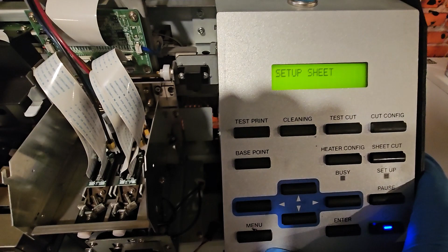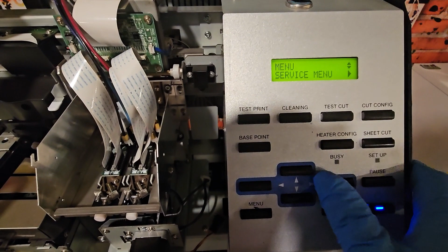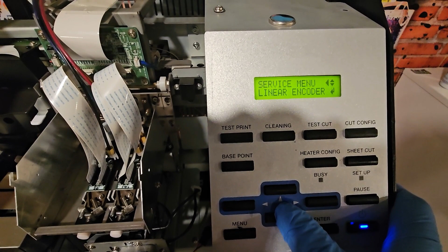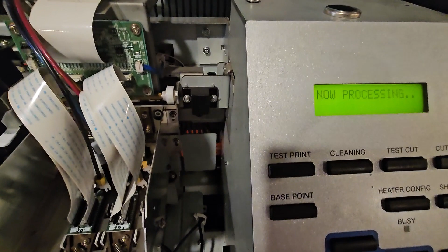All right, so right now we're in service mode. If you're not familiar with service mode, go ahead and look at my other videos. I'll show you how to get into the service menu. So we're gonna go to menu, service menu, then I'm gonna go down here to, let's see, linear encoder, and I'm gonna hit enter. Okay, it's telling me to lower the pinch roller, so I'm gonna go ahead and do that. All right, we're gonna test the encoder, make sure it's reading properly right now.